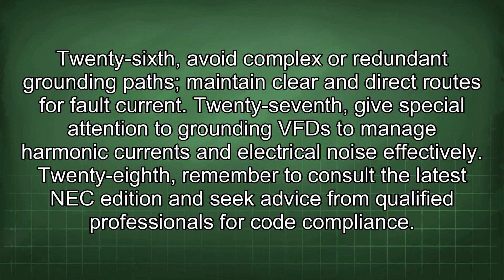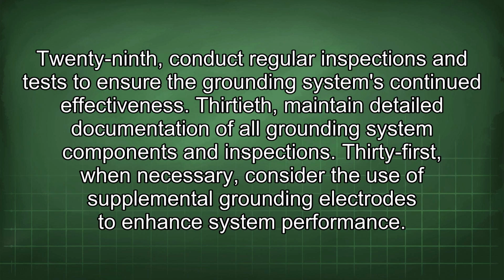26th, avoid complex or redundant grounding paths, maintain clear and direct routes for fault current. 27th, give special attention to grounding VFDs to manage harmonic currents and electrical noise effectively. 28th, remember to consult the latest NEC edition and seek advice from qualified professionals for code compliance. 29th, conduct regular inspections and tests to ensure the grounding system's continued effectiveness. 30th, maintain detailed documentation of all grounding system components and inspections.